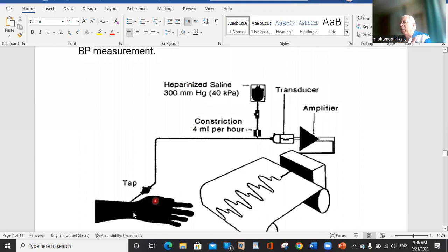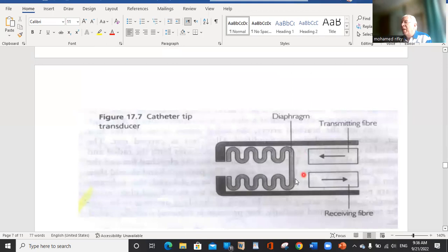And this is the direct measurement of blood pressure. This is the radial artery, and this is the continuous measuring of pressure up to 300 millimeter mercury, and we have a constriction to give 4 millilitres per hour for continuous flushing. And this is the amplifier, and this is the transducer. You see the amplifier, of course, is drawn in a triangular shape. Of course, these are affected or could induce a frequency which enters the frequency of the normal blood pressure measurement, and will induce what we call resonance. This I forgot to tell you.